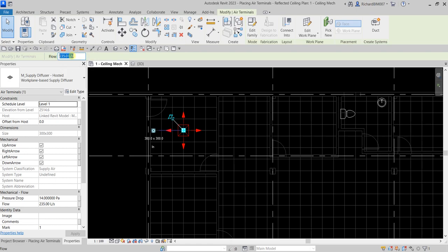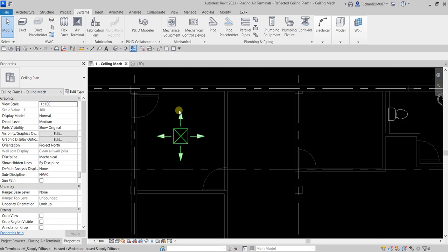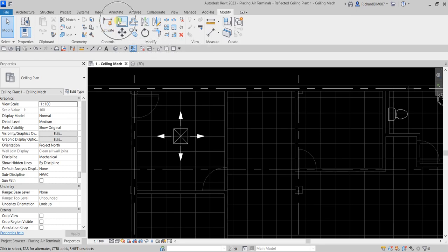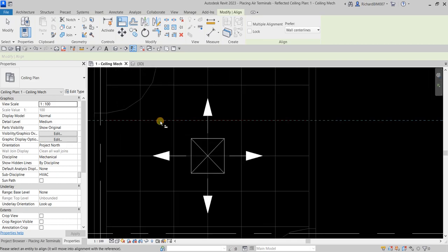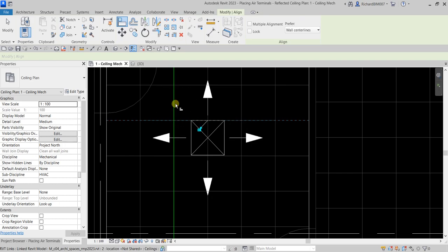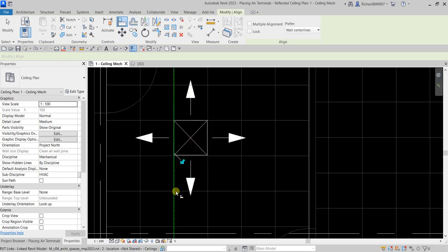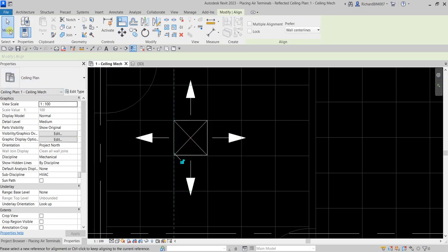From the Options Bar, change the flow rate — I'll set this to 150 liters per second, which is around 300 CFM. To align it to the ceiling grid, use the Align tool: go to Modify, click Align, click the reference line, then select the side of the air terminal you want aligned to that line.